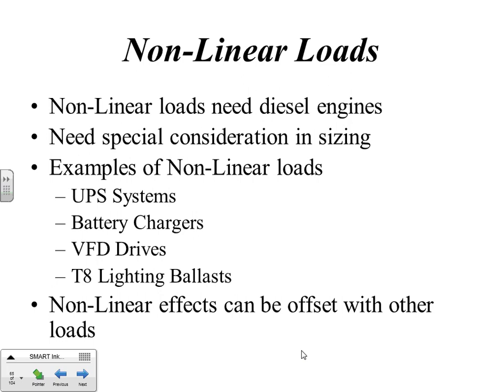Types of nonlinear loads that you're going to see are UPS systems, battery chargers, VFD drives, which are becoming more and more common on motors, and T8 ballasts and fluorescent lighting. Nonlinear effects can be offset with other loads. A good example of that is Time Warner Cable, when it was still Time Warner, called me in. Their engineers were having an issue at the Eden Prairie site, and they had just about 100% nonlinear on there. For a test, and I kind of suspected that based on what they had already told me, we brought a portable load bank with us.